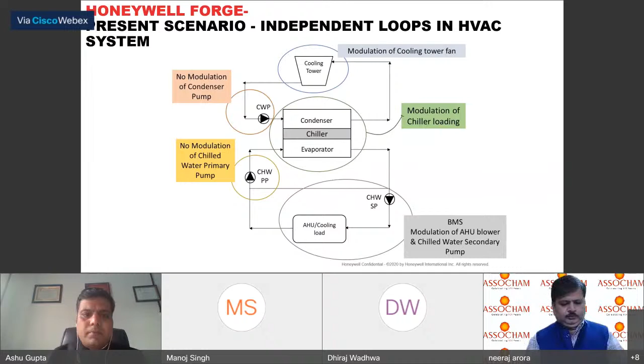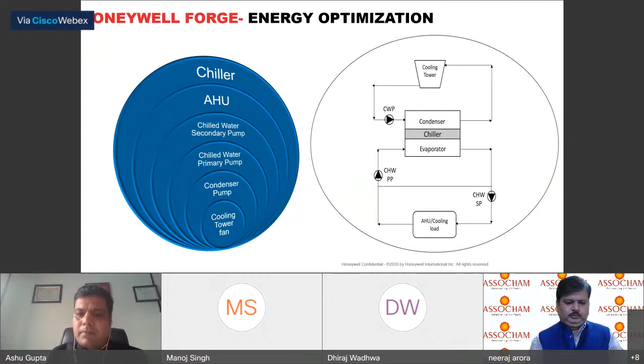This is a normal BMS system. Now the chiller, cooling towers, chilled water and condenser pumps—these are independent systems, not talking to each other. So with an integrated plant management system, you can have these things connected. This is what we mean by integrated plant, or the Forge technology—we consider all these systems, including AHUs and low side, as a single system. All parameters should be connected so we understand how your chiller, pumps, cooling tower, and AHUs are connected and loaded, so it can deliver maximum savings.